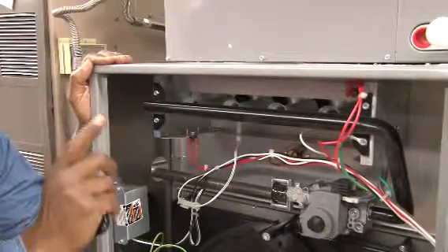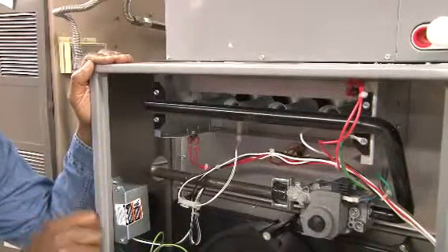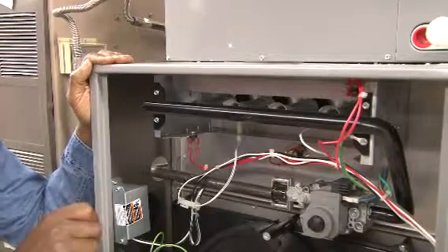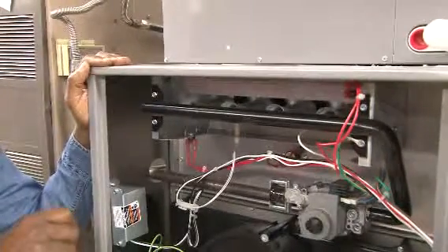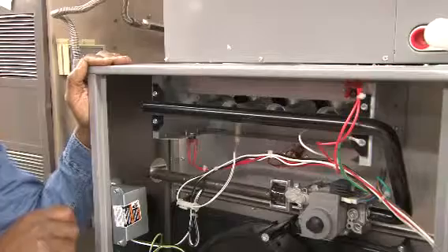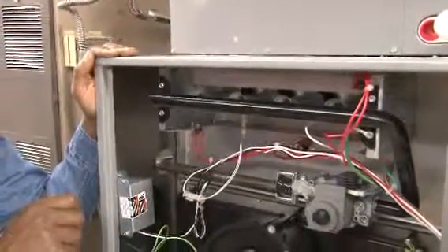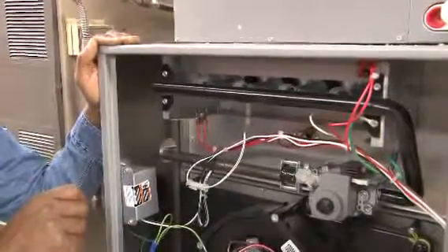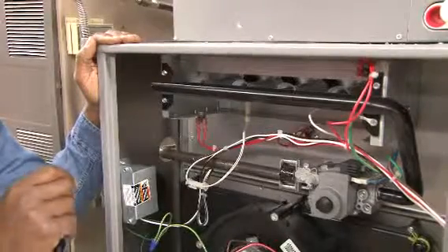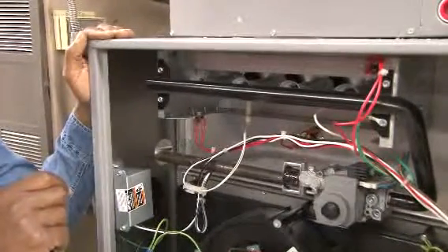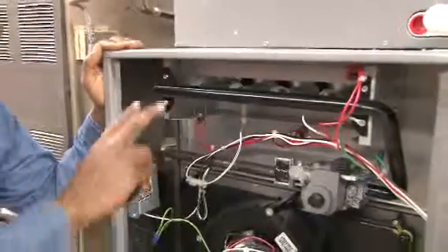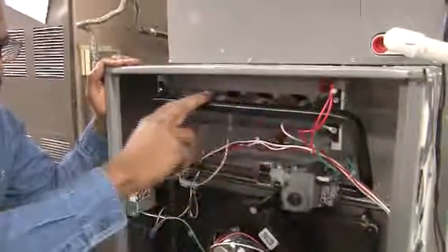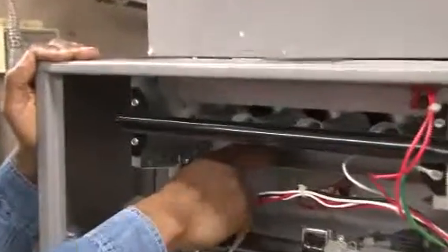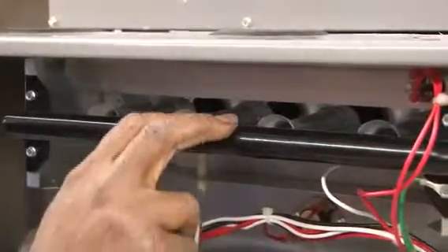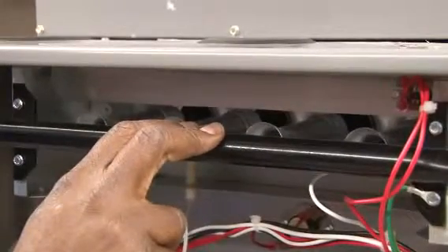This is a 90% efficiency furnace, and this furnace is designed to extract up to about 90%, a little bit more, of the heat that you're consuming and put it into the house, compared to some older furnaces that actually use a lower percentage. Now, the components of this furnace: here is the burner section, and behind it is the combustion section, where the flames actually shoot a flame inside of the combustion chamber.